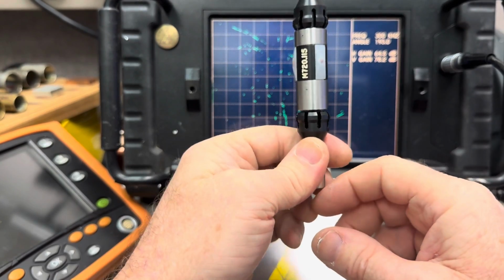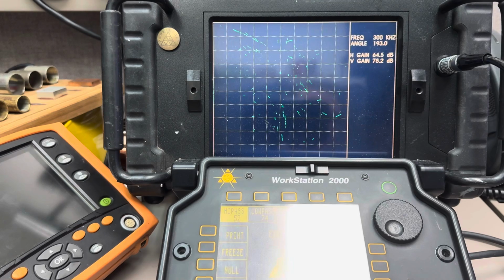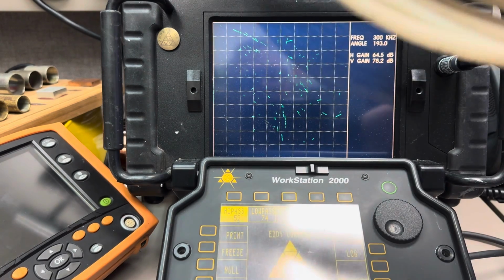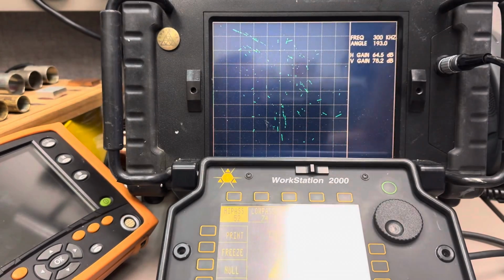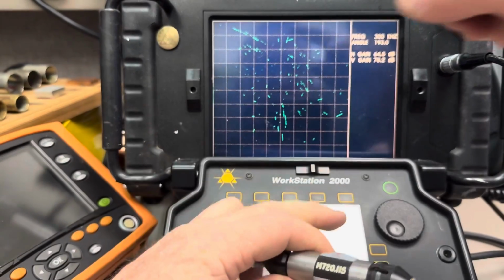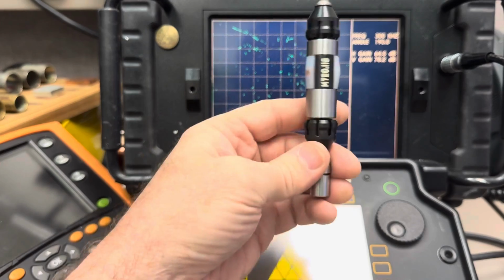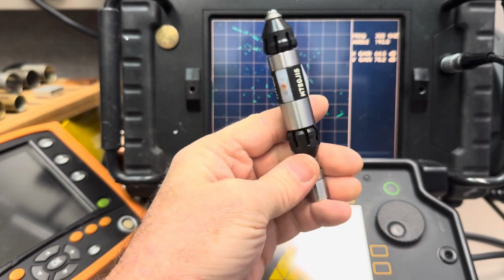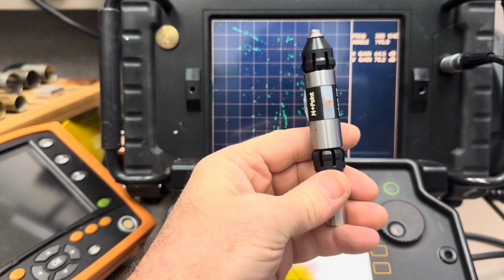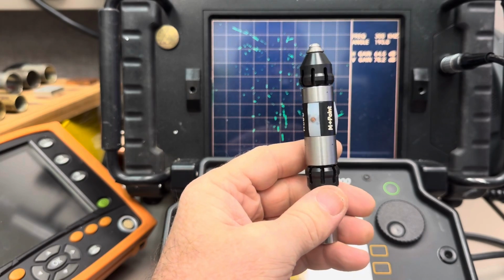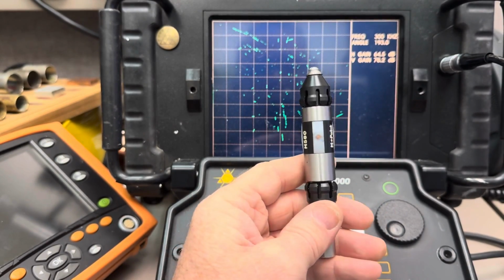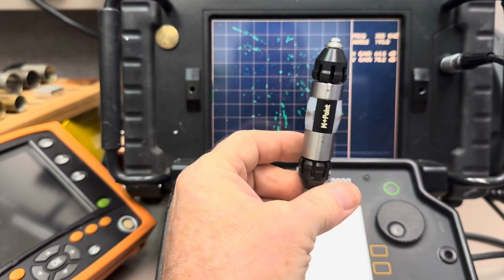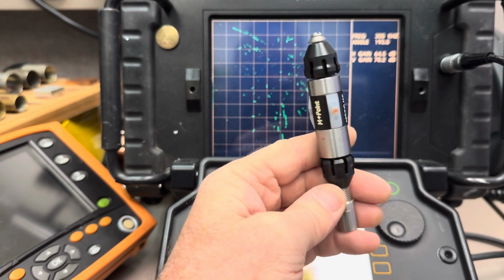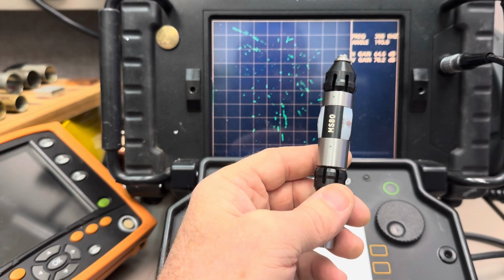All right, so this would attach to a motor unit. Heat exchanger tubes are long, right? So you've got probe shafts like this that are like 100 feet long. And on the end of that probe shaft, or poly they call it, you'll attach a motor unit, which is probably about a foot long or so. And then you attach the probe head onto that motor unit, and you would control it from your data acquisition station. So you can adjust the rotation speed and also the indexing speed, which is in and out. And a combination of your rotational speed and your indexing speed, you will arrive at a tube pitch, which is the distance that the probe travels between rotation. And you always want to make sure you get plenty of overlap, so you have to calculate what your scans are going to be like.